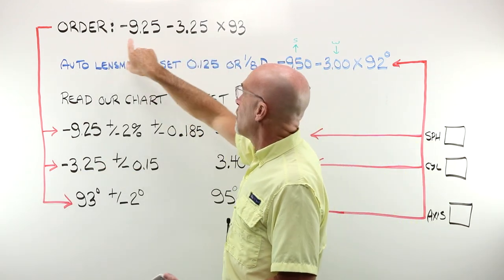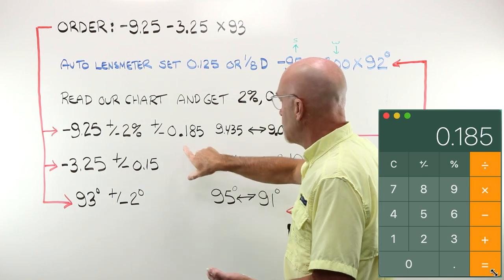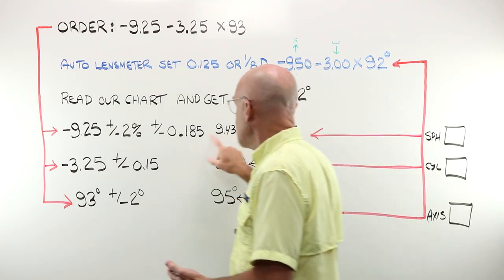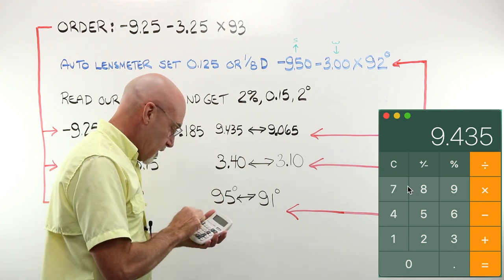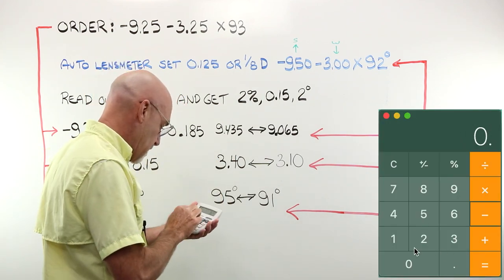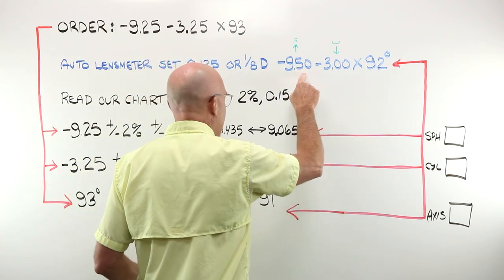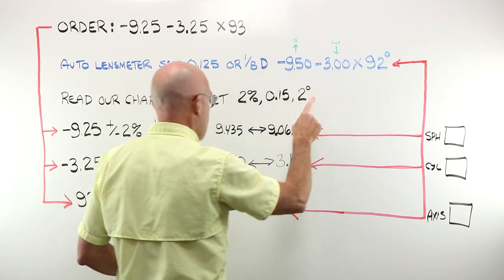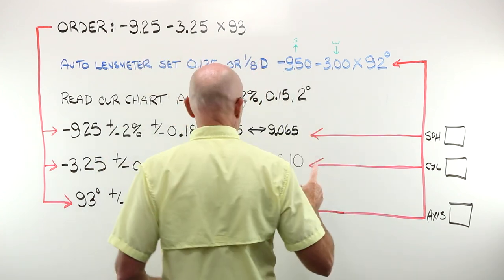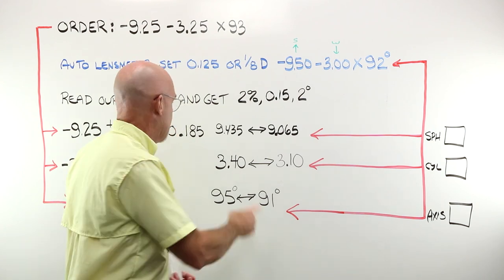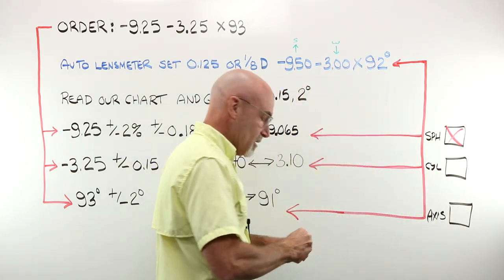We are taking the tolerance for what we actually wanted. 9.25 times 0.02 gives us our two percent, which is plus or minus 0.185. 9.25 plus 0.185, 9.435. 9.25 minus 0.185 gives us 9.065. Does what we actually got minus 9.50 fall between here and here? The range of tolerance of two percent plus or minus for the 9.25 we actually wanted? No, it doesn't. Out here or someplace, it's no good. No, the job would not pass for sphere power.